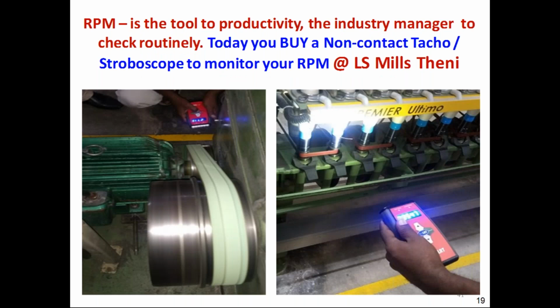RPM measurement: many people are still using the centrifugal tacho or this non-contact tacho. For this non-contact tacho, you have to switch off the machine to measure the RPM. Otherwise, you use the stroboscope type, which costs only less than 20,000. You give it to your energy audit team person and ask him to go around for 1 hour. He can measure the motor speed and machine speed, for 30 or 40 machines in 1 hour. You don't need to switch off the machine, but you can measure it.